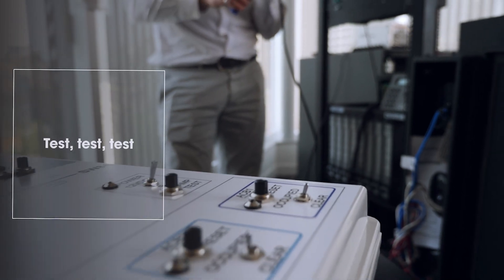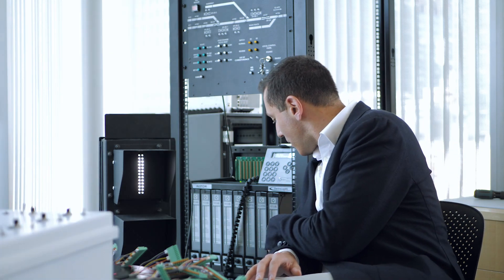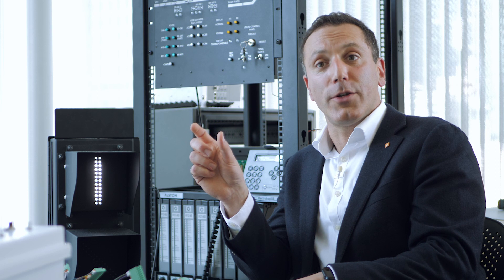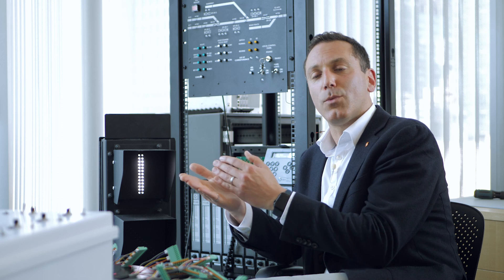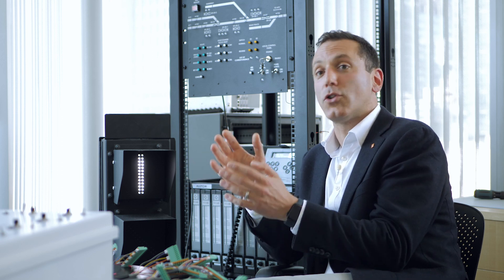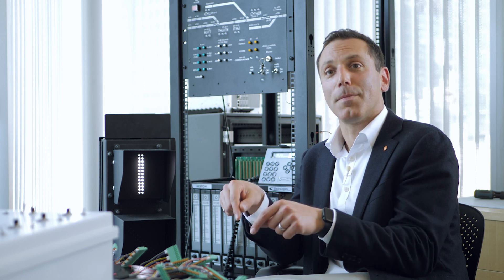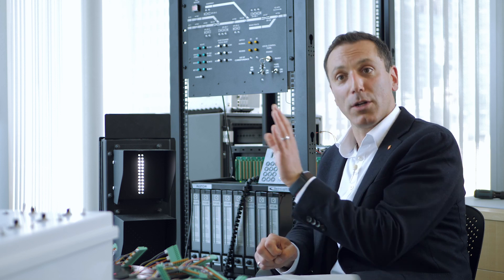The test panel enables us to test, demonstrate, and simulate every piece of I/O coming out of this power supply. We're able to test every line of configuration we're making to the interlocking here. As part of our validation process, we create test scenarios and try to break the system — we want to break the system here in this lab before it goes anywhere near the railway. We'll be doing what's called a factory acceptance test here in this lab. We have all the hardware as a complete simulation — a complete one-to-one mirror of what's going to be put in the field. All paid for out of Stantec's pocket.